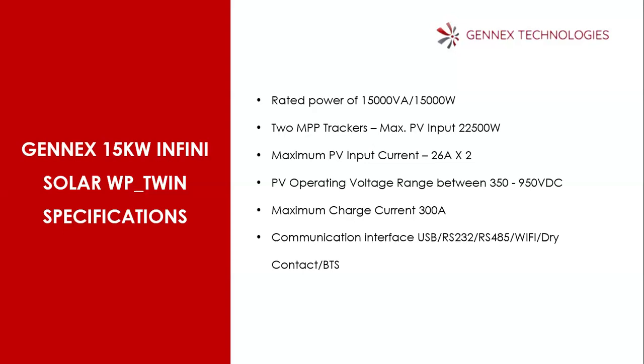So the 15 kilowatt Infini solar inverter is a dual output inverter, and it is a grid tie or on-grid type of inverter, which allows you to do a sort of mini grid and feed in to grid function. It has many new features and new technologies that enhance solar generation. At the start, it is rated as 15 kilowatts, which is 15,000 VA, the same as 15 kilowatts, with a power factor of 1.